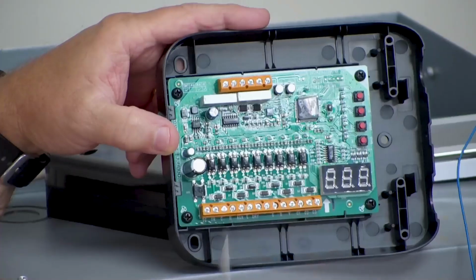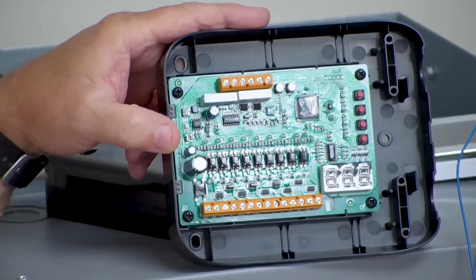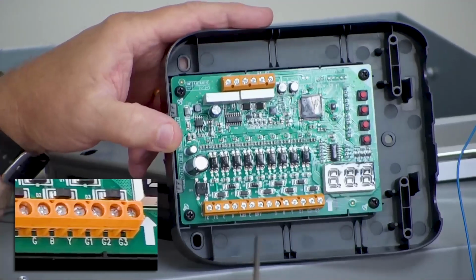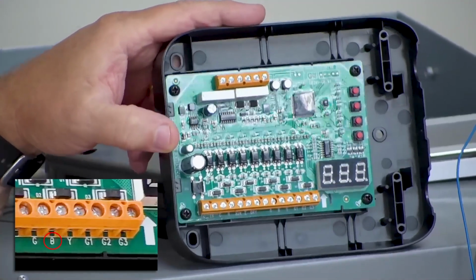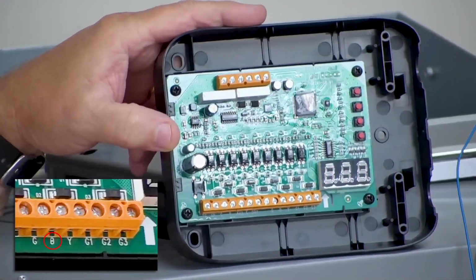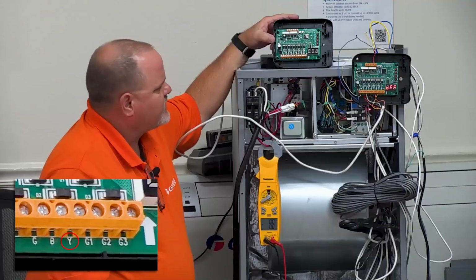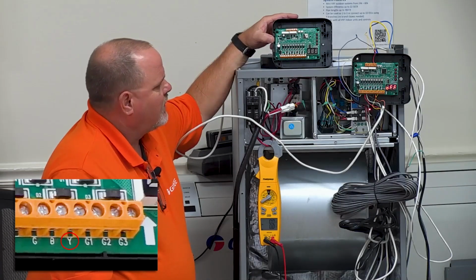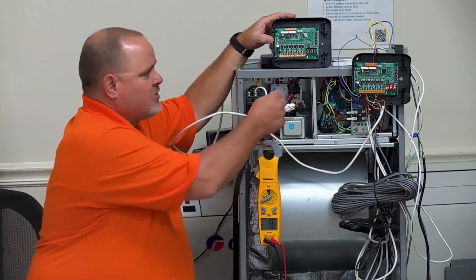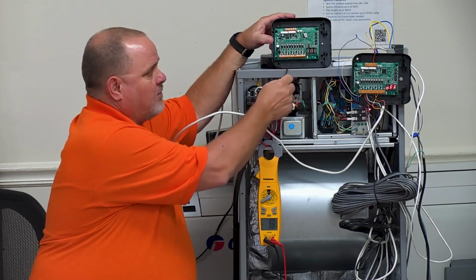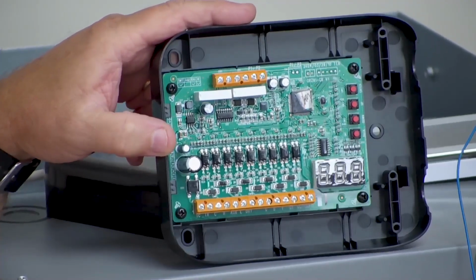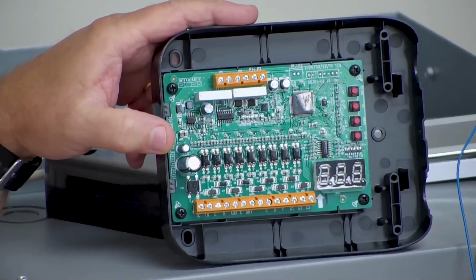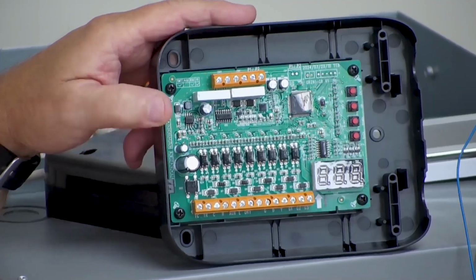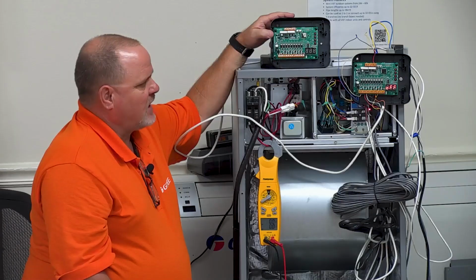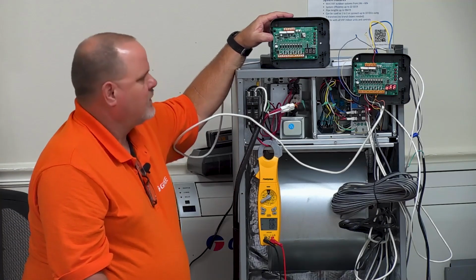And again, we can go in there and set that P code, and I'm going to explain that a little bit further. Remember, B is your reversing valve, and that's for heating mode. And in your Y connection, just like any other unit. So again, this 24-volt adapter is really built and designed to go with a GREE air handler, which is also going to give you better electric heat control. It's not really designed to go with a third-party air handler.